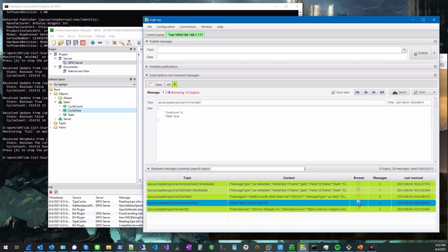So if you have a huge number of devices and you don't see the need for a lot of metadata in your messages, you can strip them down to minimize the network overhead and only send that information. And when this is converted into a binary format, it gets really compact. This would probably be less than 10 bytes in size. And this is an important feature that they're using for the UAFX effort, where they expect to be able to develop hardware which is capable of producing and consuming UA PubSub messages.